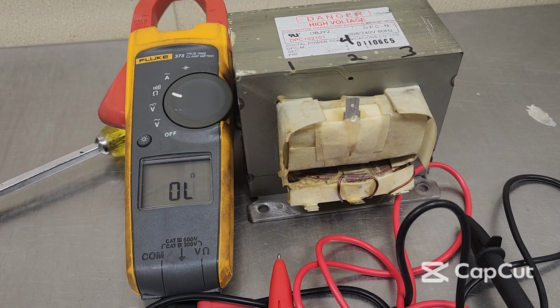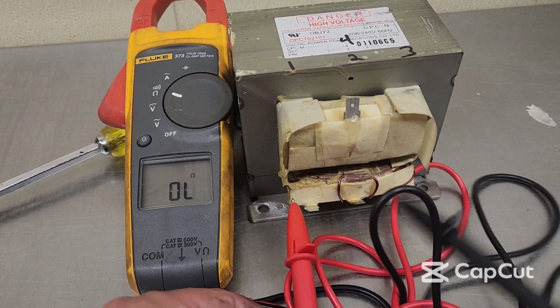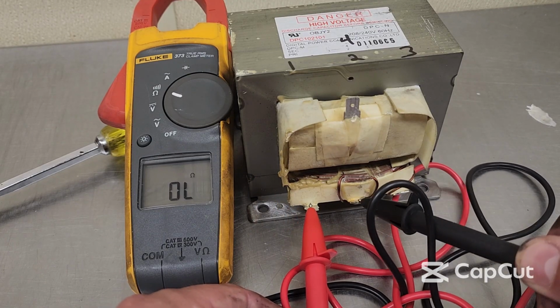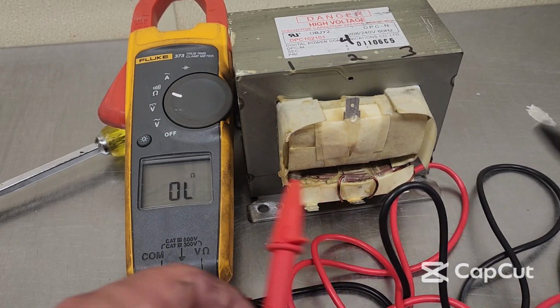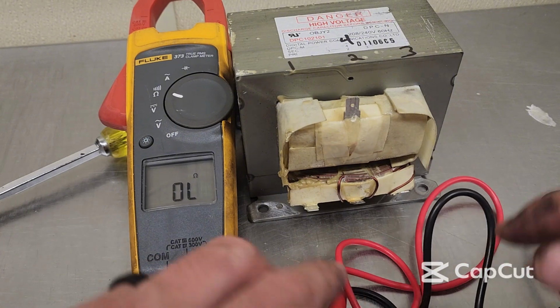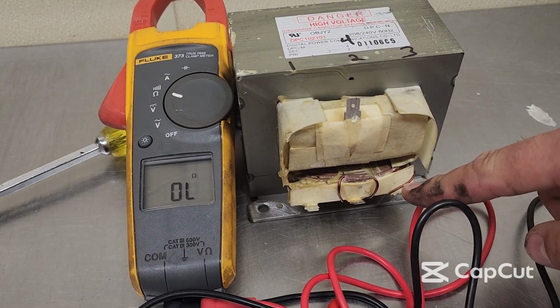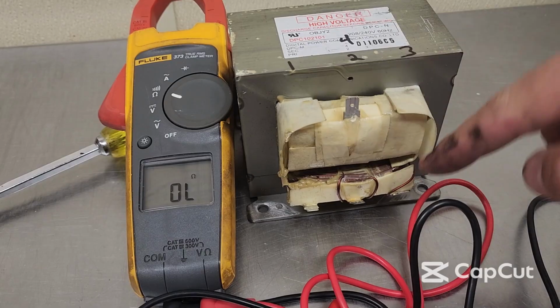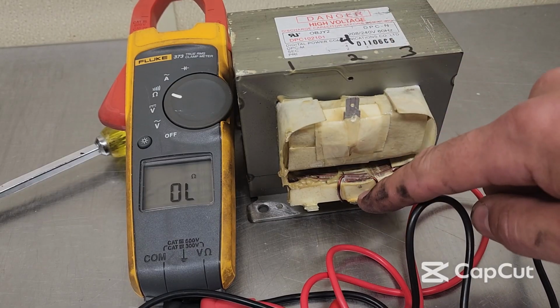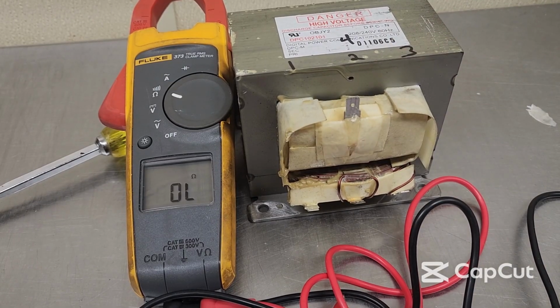And the other thing too is this is a really good place to show, we were talking about the K6 probably 4 episodes or 5 episodes ago. This shows the taps that K6 switches between. So it's going to be switching between 2 and 3. So if that voltage sense module is sensing 240 volts, it's going to send voltage to our tap 3 versus sending voltage to our tap 2 for 208 volts. So the more you know, right?